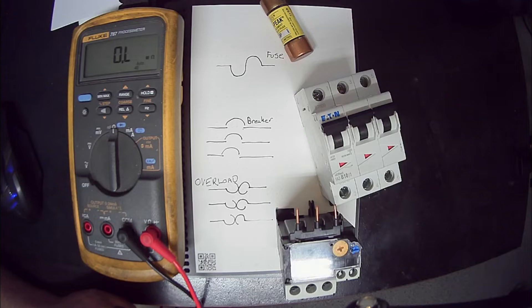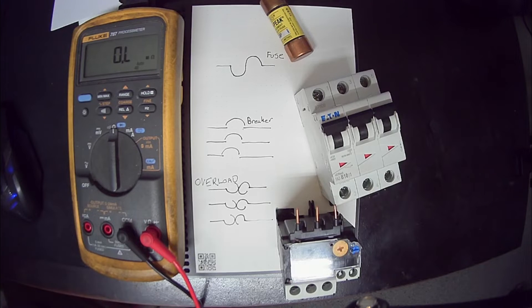So in some cases, like on the input of a drive, some drives can only really have a fast blow type of fuse and that's to prevent damage to the drive. Most overloads are kind of in their name - whether it's a fuse, a breaker, or motor overload, they all kind of work the same ways. They're trying to protect the equipment and the wiring.